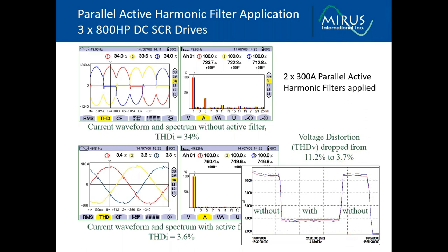As mentioned earlier, the main issues with active front end or active harmonic filters are their reliability and the fact that they inject high frequency harmonics due to this switching. In this particular application, I've been made aware that these active filters are no longer in operation. They've been disconnected. I'm not exactly sure why, but there are often issues associated with active harmonic filters that require their disconnection.